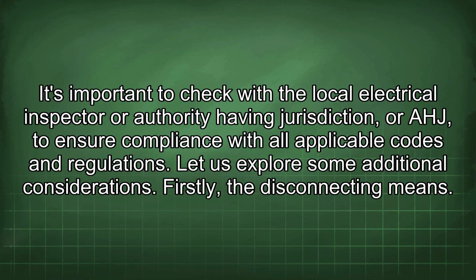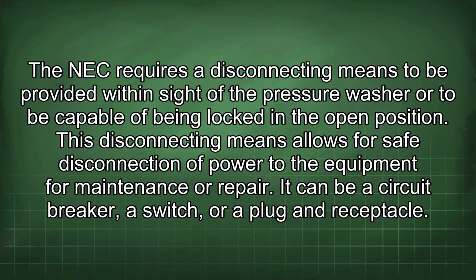Firstly, the disconnecting means. The NEC requires a disconnecting means to be provided within sight of the pressure washer or to be capable of being locked in the open position. This disconnecting means allows for safe disconnection of power to the equipment for maintenance or repair. It can be a circuit breaker, a switch, or a plug and receptacle.